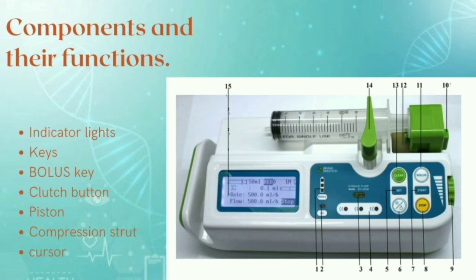Next component is keys. Mainly there are 5 keys available. First one is set key. We use this key to enter or quit the mode parameter setting interface. Second one is start key. Its function is to start the injection.